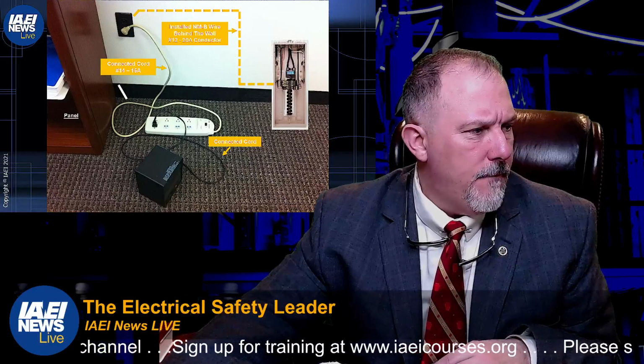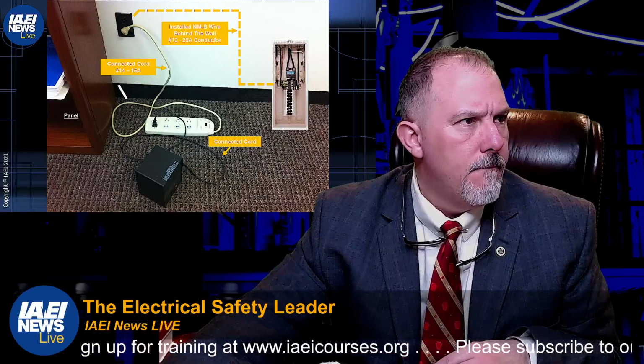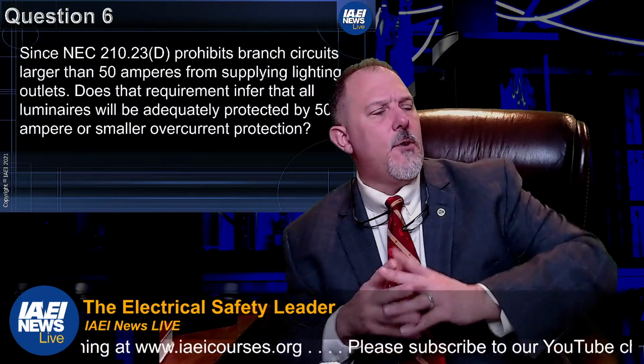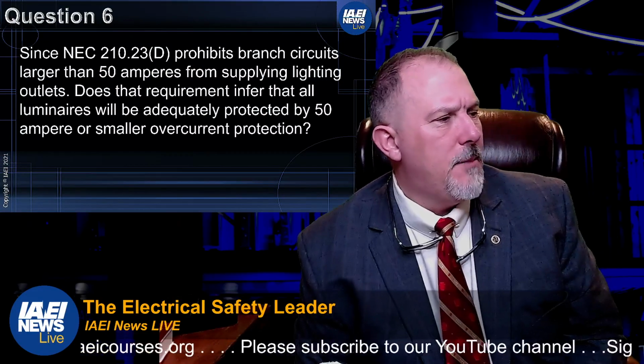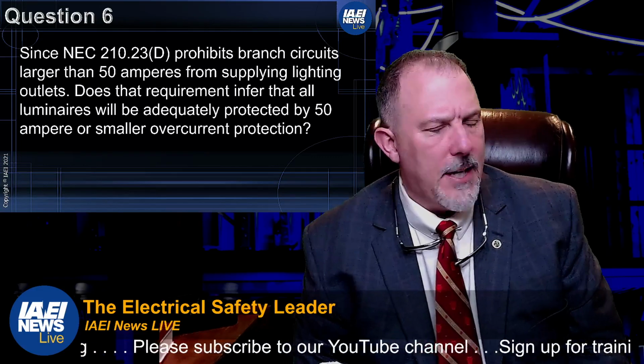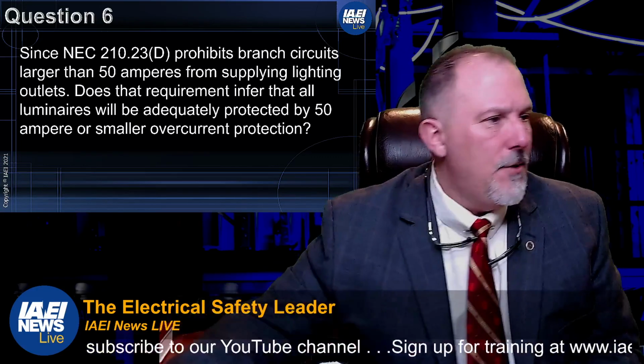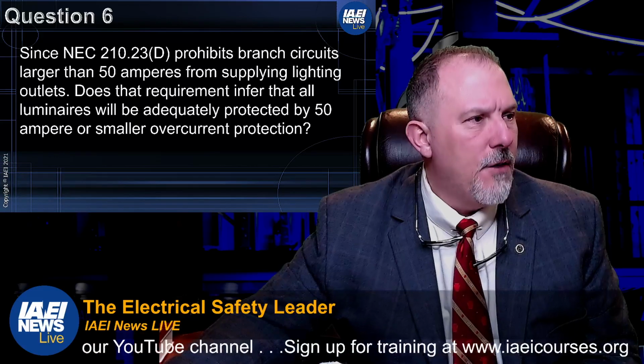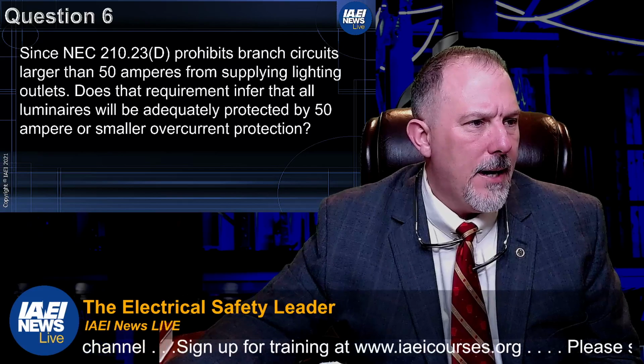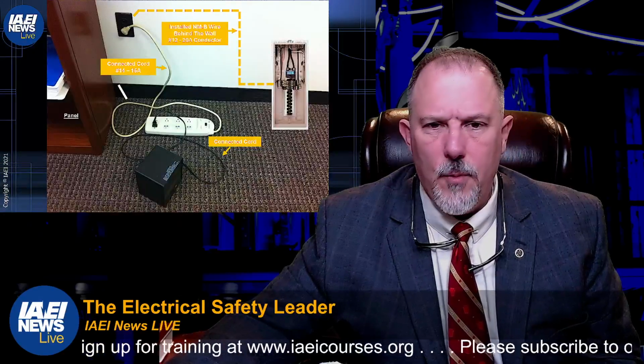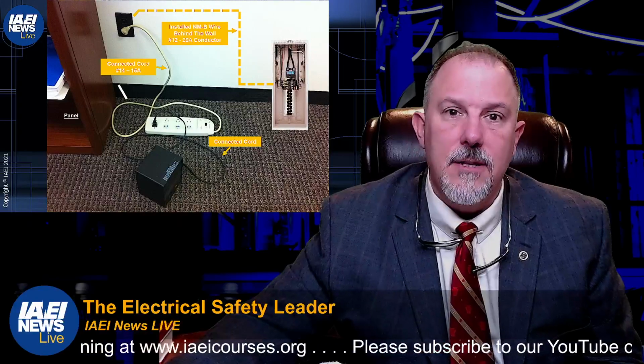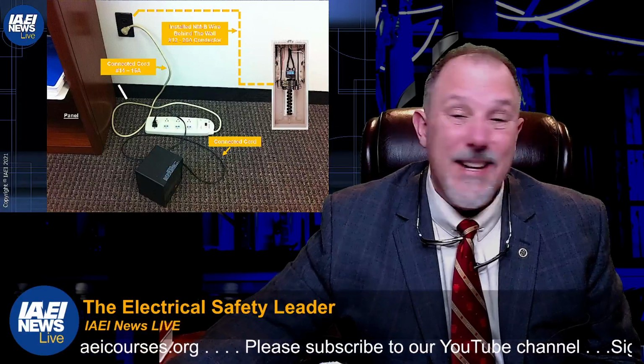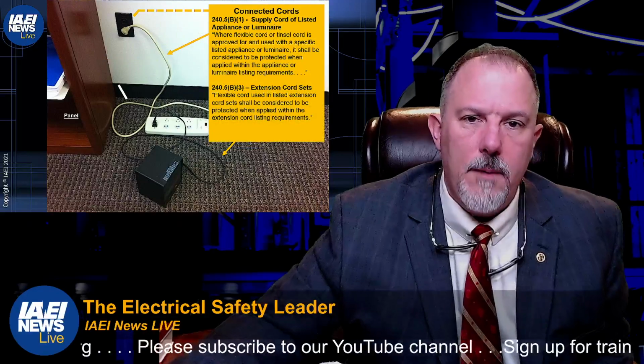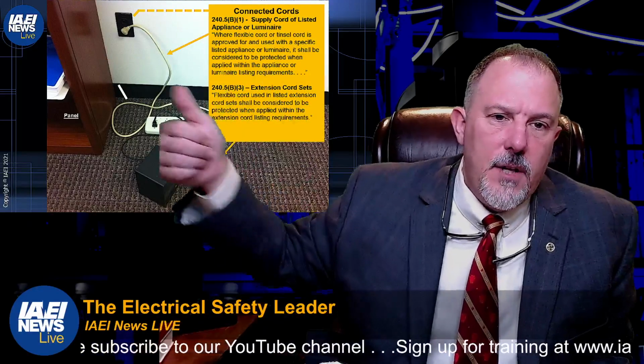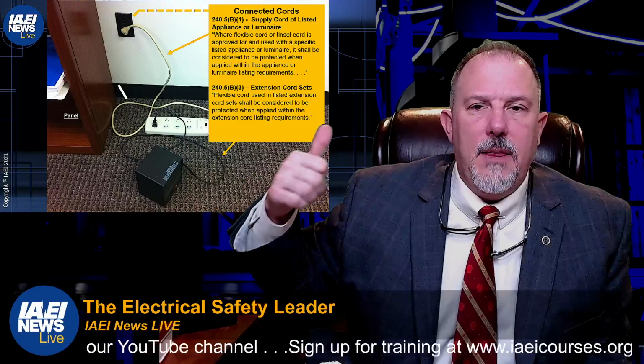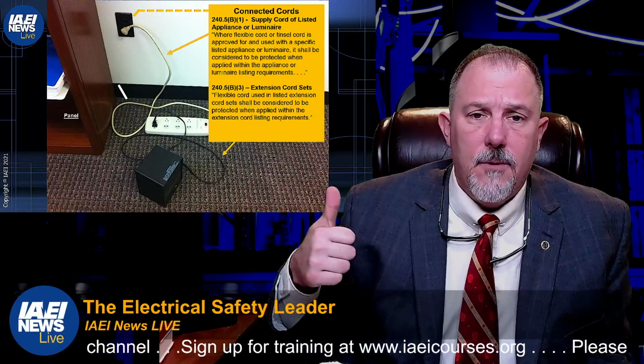Let's go back to that question. Does that requirement infer that all luminaires will be adequately protected by 50 ampere or smaller overcurrent protection? I can tell you what the overcurrent protection is there for, and I can explain what parts of this circuit that overcurrent protection does provide protection for and what it does not. In 240.5(B)(1), these cords are not protected by the overcurrent protective device. Because why?